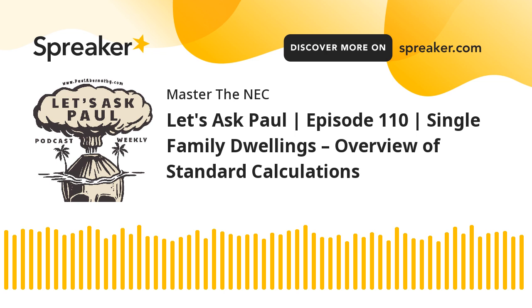There's different parts to that, but that's how you calculate the general lighting and general use receptacle and small appliance and laundry calculation, okay? Now you move on to the next thing. You write that down. The next thing you're going to move on to, okay, is what's called fastened in place appliances. Okay, so it's the next logical step. And the fastened in place appliances are going to be under 220.53. And this is pretty straightforward. If you're in the 2020 code, it did add some clarity to it, but it's pretty straightforward.